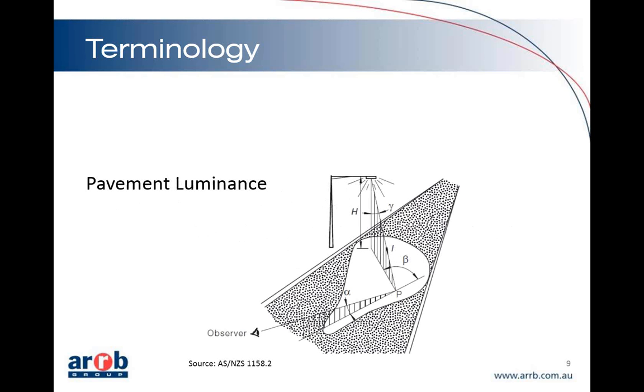Talking about pavement luminance: the mid-block sections of road you design to for pavement luminance, and that has an observer position which is 60 metres away from the area that you're designing for. So you have light that comes down from a light that's on a pole in a bracket — there's a certain overhang over the road — it hits the road surface and then it's reflected back to that observer position. Pavement luminance and the difference between that and illuminance is something that I often find people get confused about.